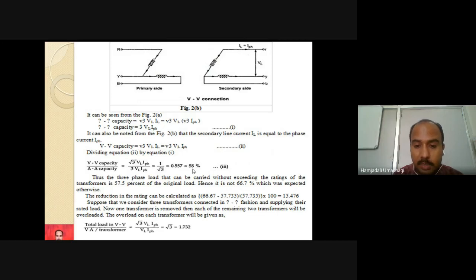If you connect the same 100% load, then there is a possibility that another transformer winding may experience some fault. Because of that, a complete shutdown of the transformer operation may take place. So whenever the connection changes from delta-delta to open delta, the load that can be carried safely by the open delta transformer is 57.7%, or approximately 58%.